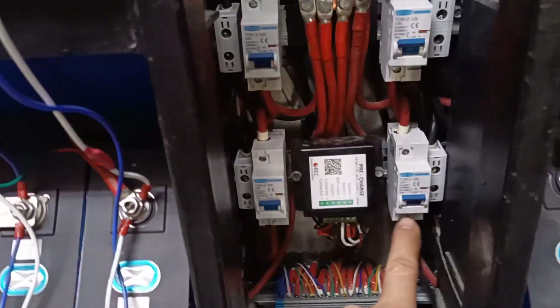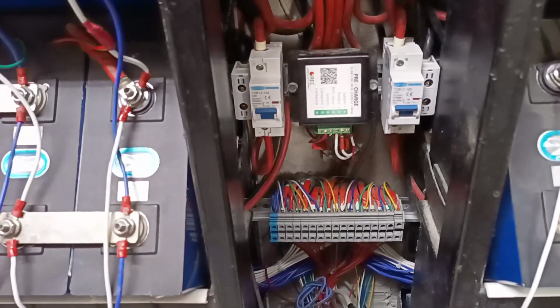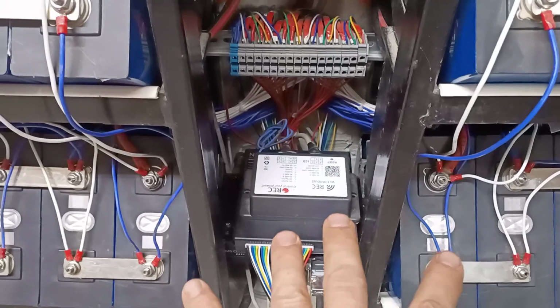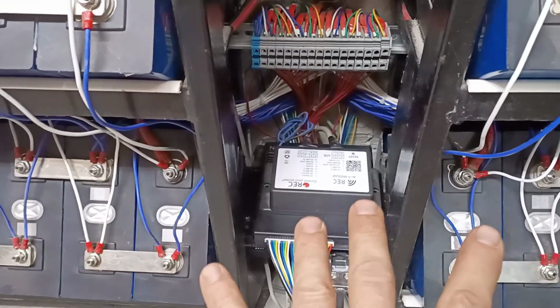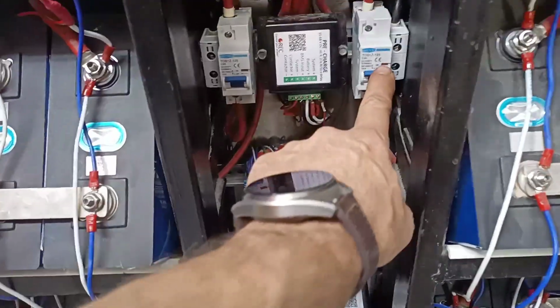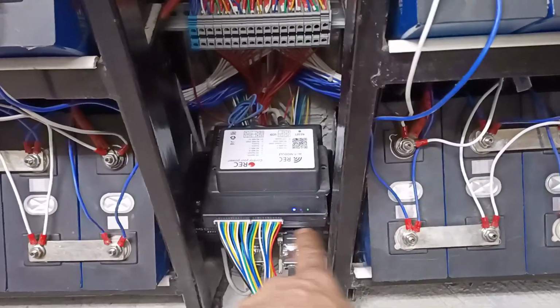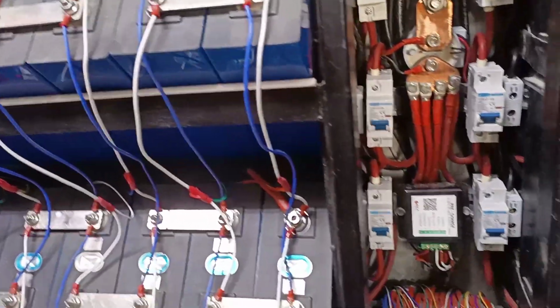That's why it's very important, for example when you work on your system, to not forget to lift the breakers. These 2 banks are always charged and discharged, because if you forget, the BMS will not read the correct voltage of the other cells, and that will be a problem.